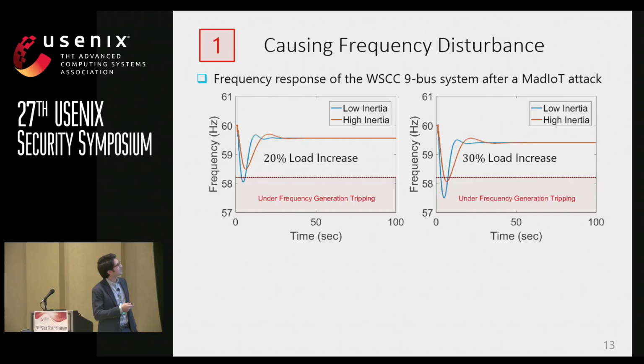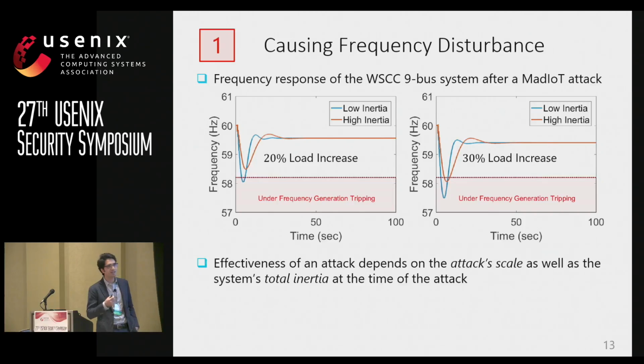For example, you'll see that when the system has low inertia, a 20% load increase may lead the frequency of the system to hit this critical under-frequency generation tripping area, which causes the generators to get disconnected from the grid and causes a blackout. We also observed that a 30% load increase in the grid led both cases to reach this critical area and cause a larger scale blackout. So the effectiveness of an attack on the frequency of the system depends on the attack's scale as well as the system's total inertia at the time of an attack.